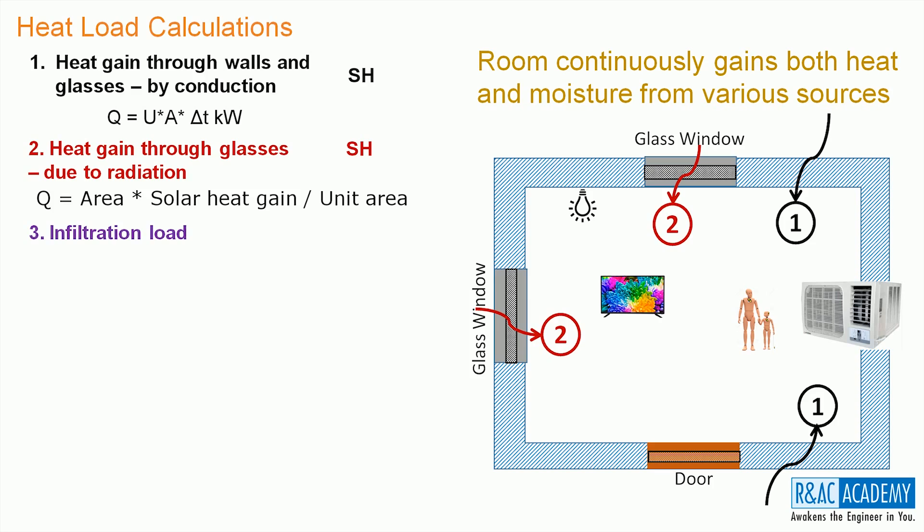The third source is infiltration load. Outside air flows into the conditioned space through the gaps and crevices around the windows and doors. The room gains both sensible heat and latent heat due to infiltrated air. First, we need to compute the infiltrated air into the room and then translate the same into latent heat and sensible heat.